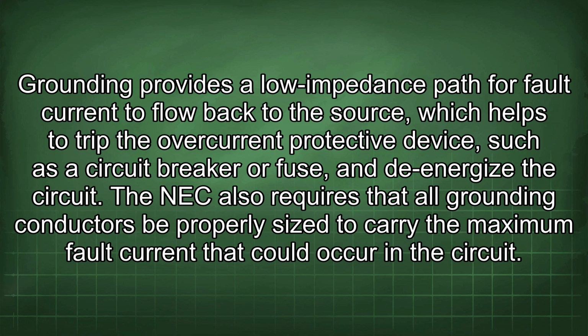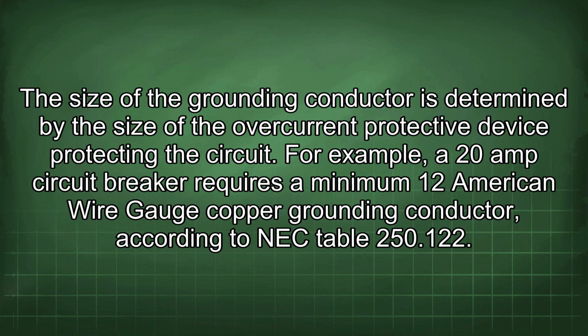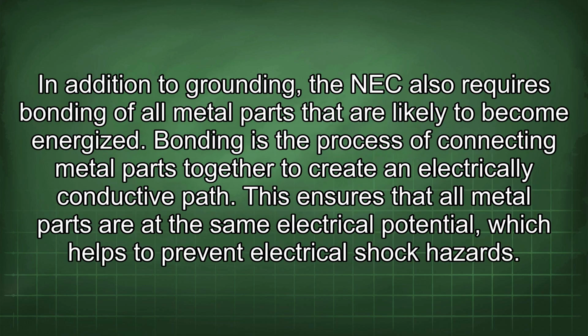The NEC also requires that all grounding conductors be properly sized to carry the maximum fault current that could occur in the circuit. The size of the grounding conductor is determined by the size of the overcurrent protective device protecting the circuit. For example, a 20-amp circuit breaker requires a minimum 12 American wire gauge copper grounding conductor according to NEC Table 250.122. In addition to grounding, the NEC also requires bonding of all metal parts that are likely to become energized.